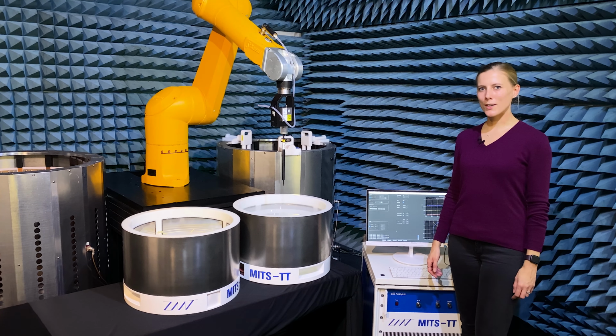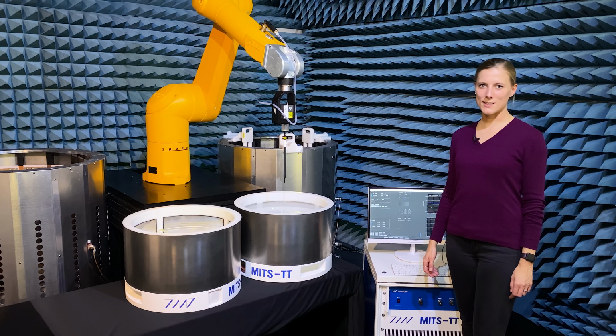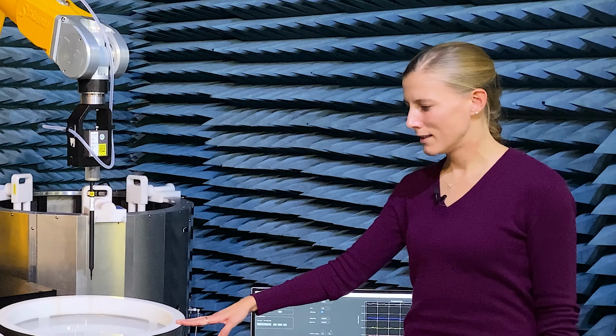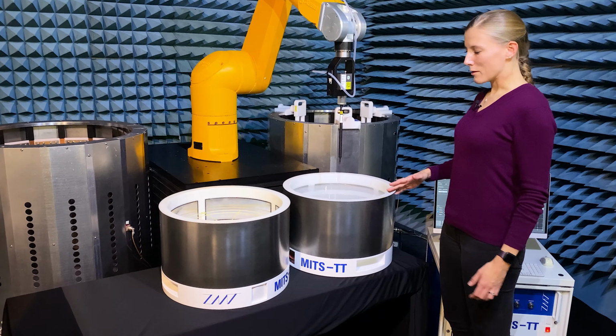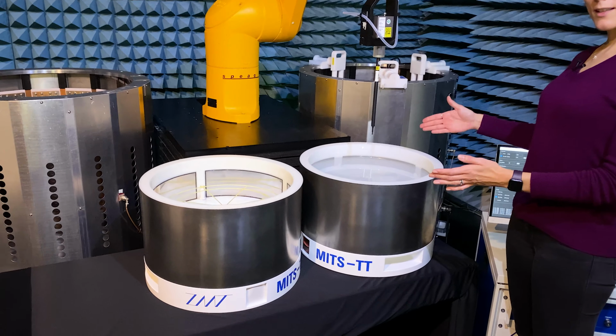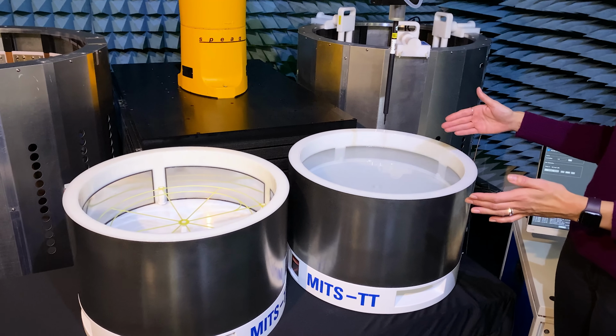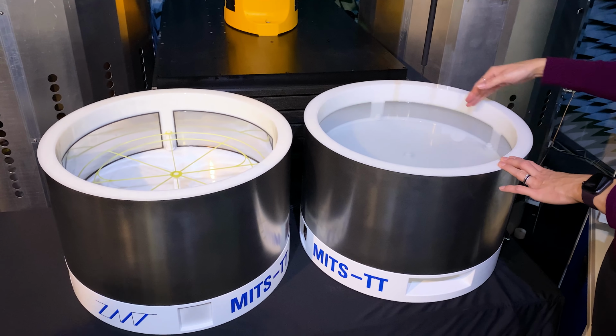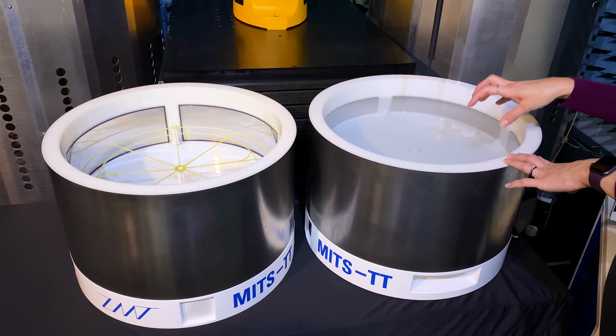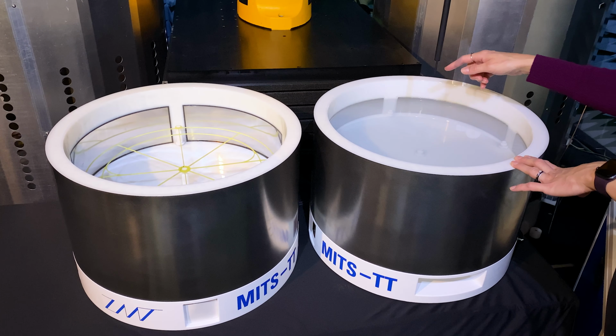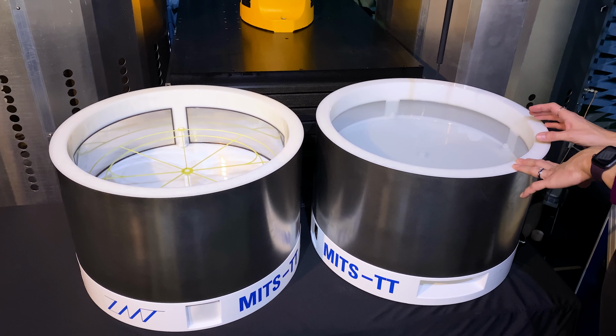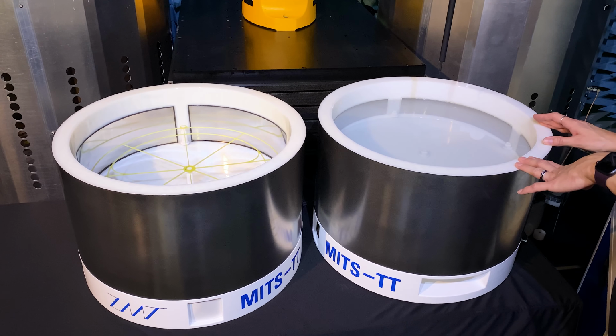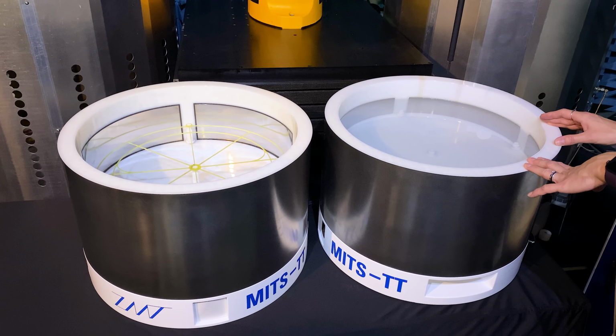Today I'm going to show you our newest medical implant test system, the MITS-TableTop, short MITS-TT, which we use for radiofrequency assessment of heating and induced voltage of medical implants. In this system, instead of having a magnetic field that induces an electric field inside the tissue simulating liquid, we use 4 electrodes to directly induce electric fields inside our liquid, in which we place a racetrack with an implant to test the induced heating or induced voltage at 1.5 or 3 Tesla.